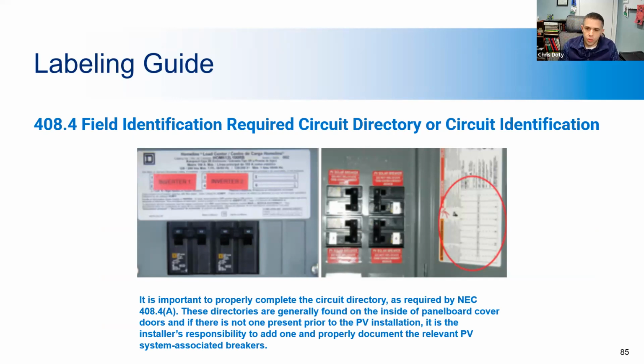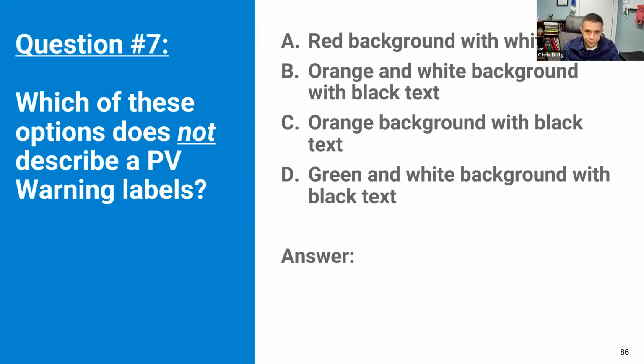Here again, we see the requirement for identification of circuits. This person didn't label the circuits, which is a no-no. The whole point of that is to assist future electricians in their maintenance and troubleshooting work, and so the homeowner can then shut the system off if they need to. This is not part of the solar code, it's part of the general electrical code, which has to be followed for solar as well.